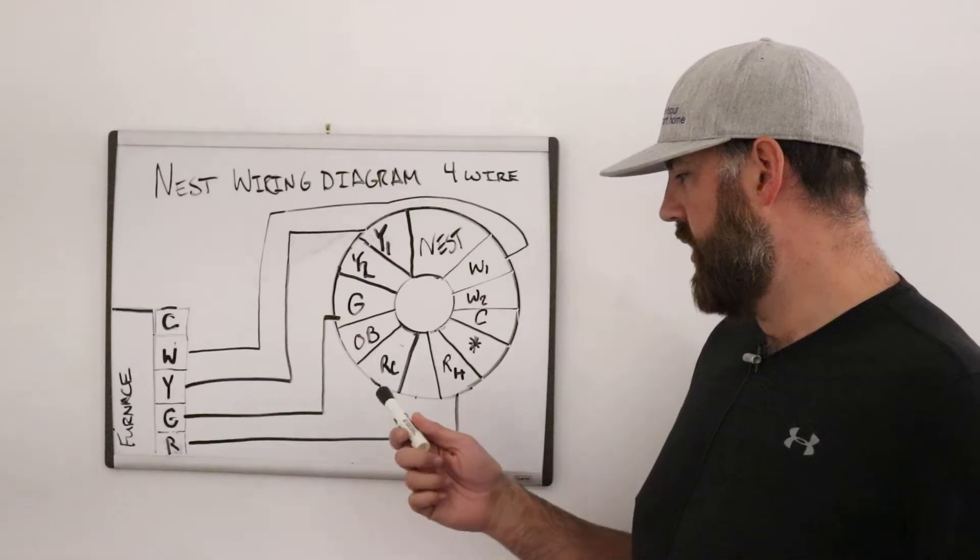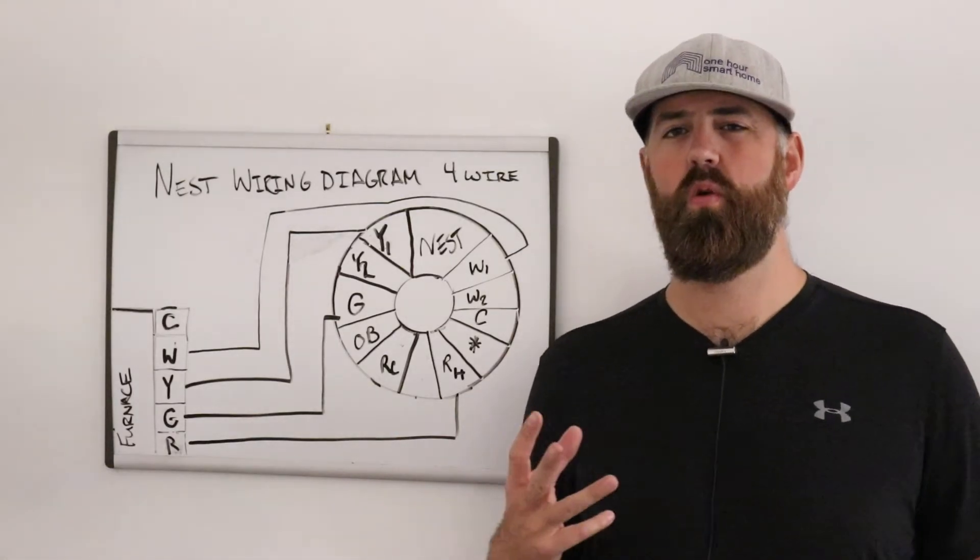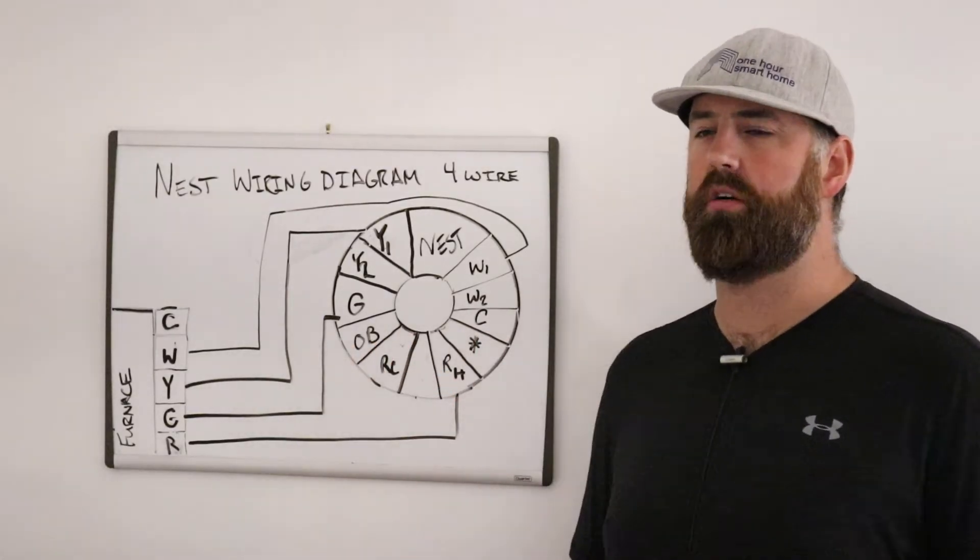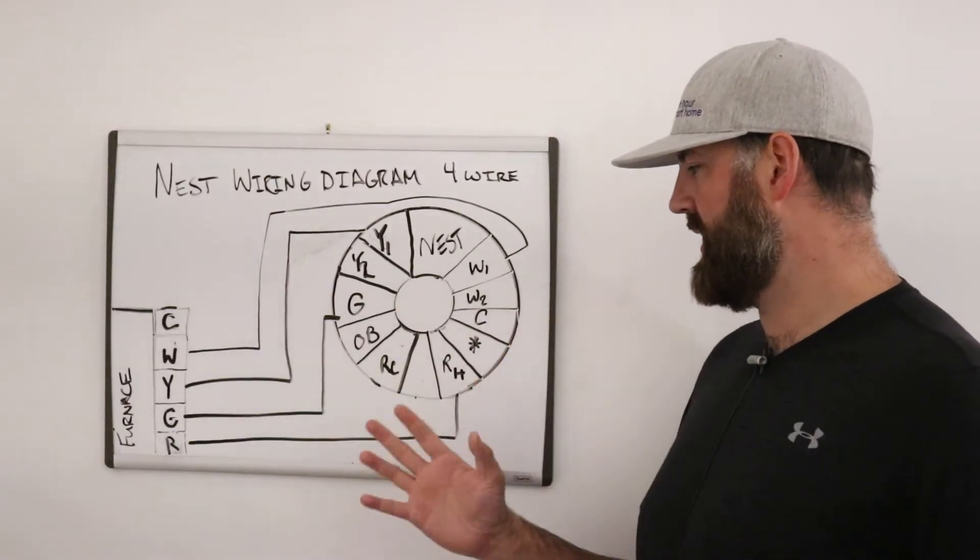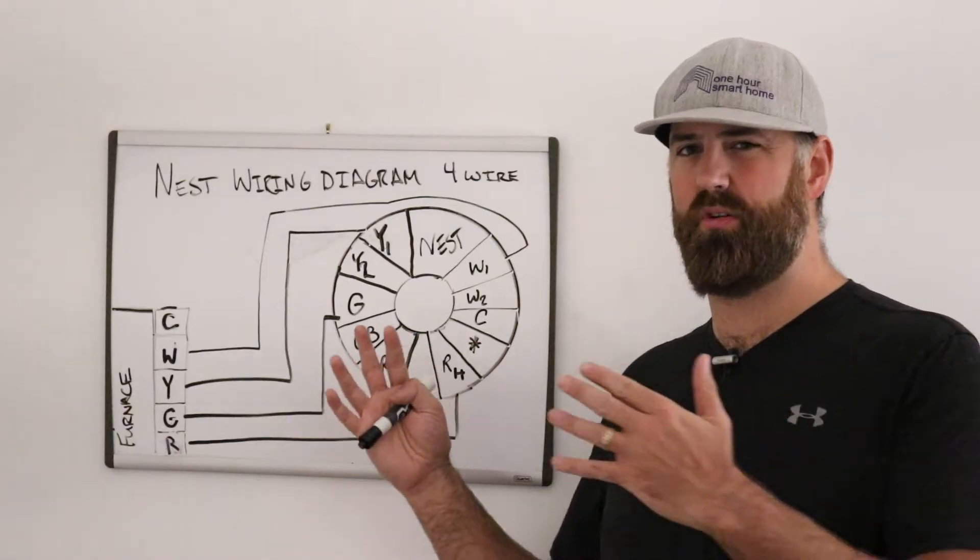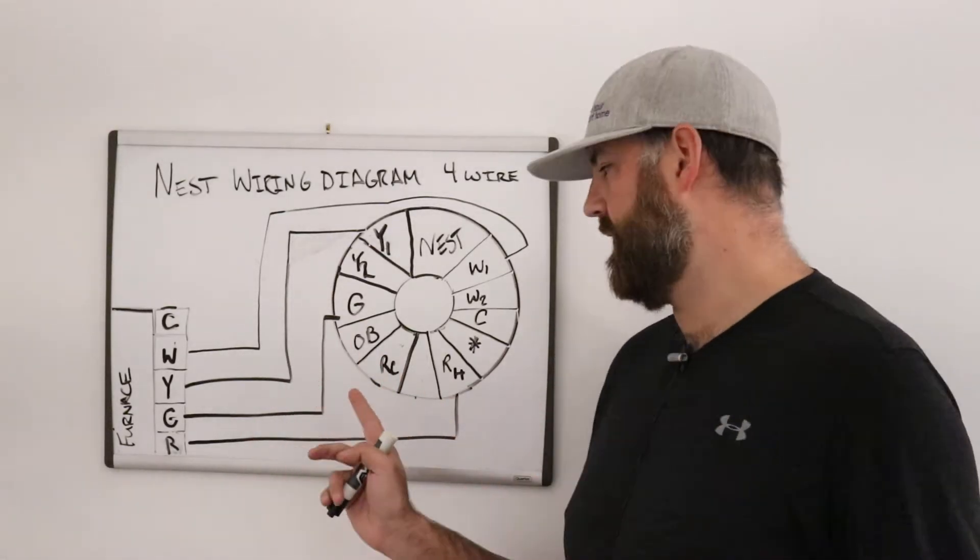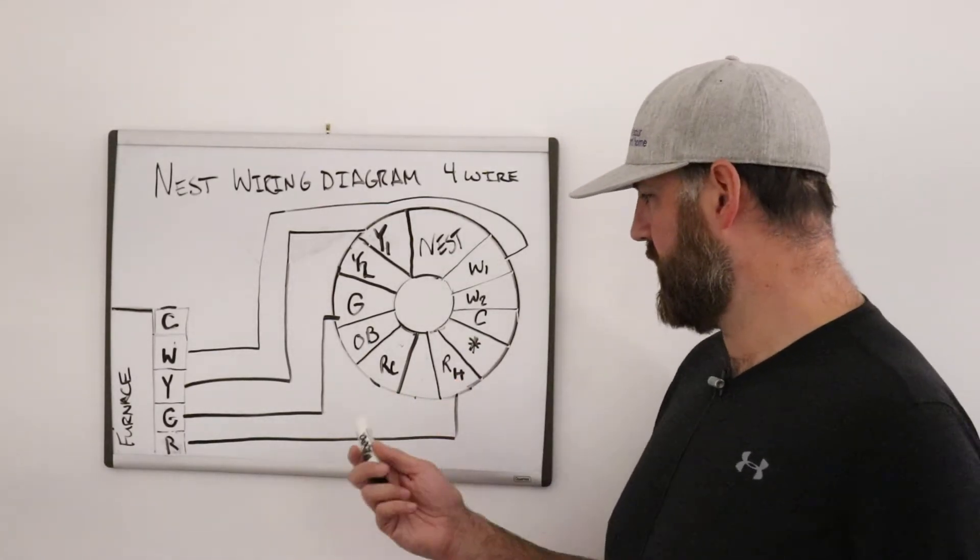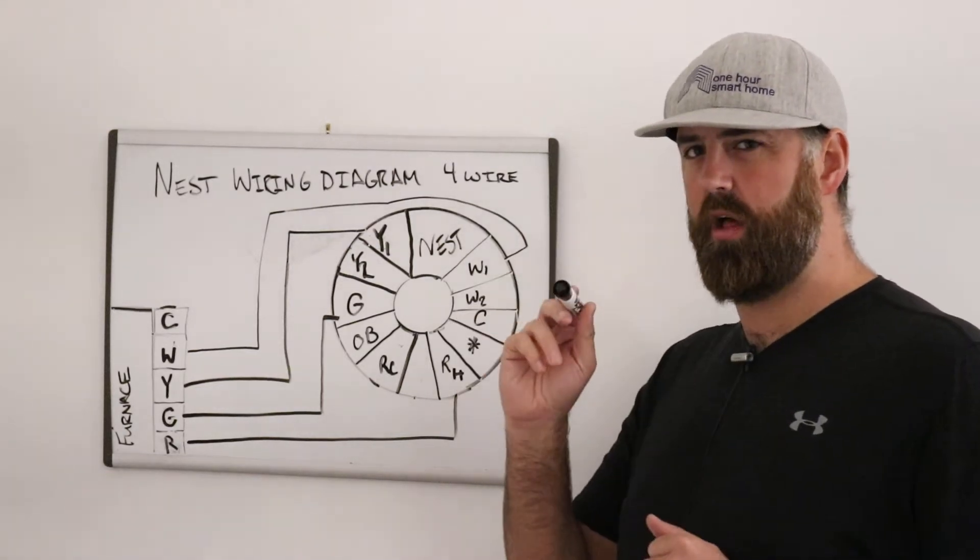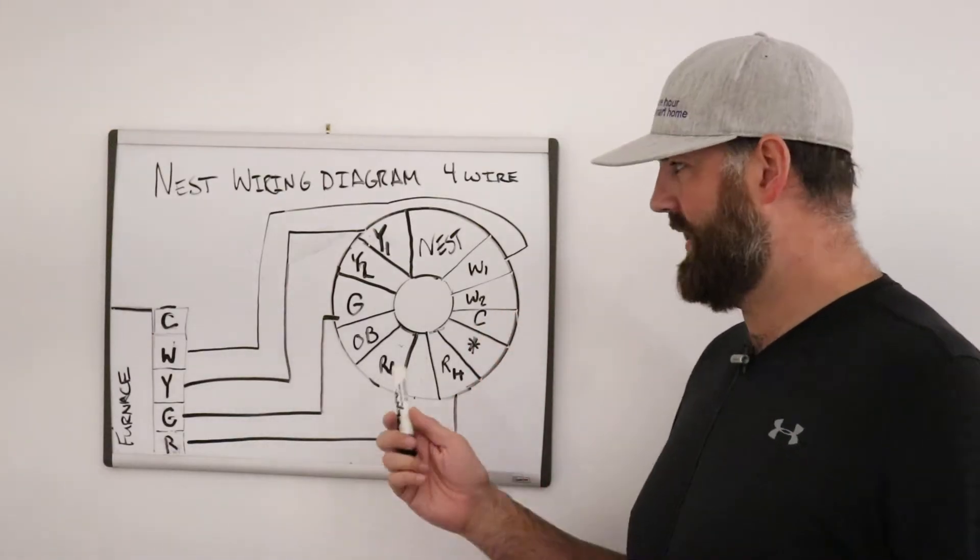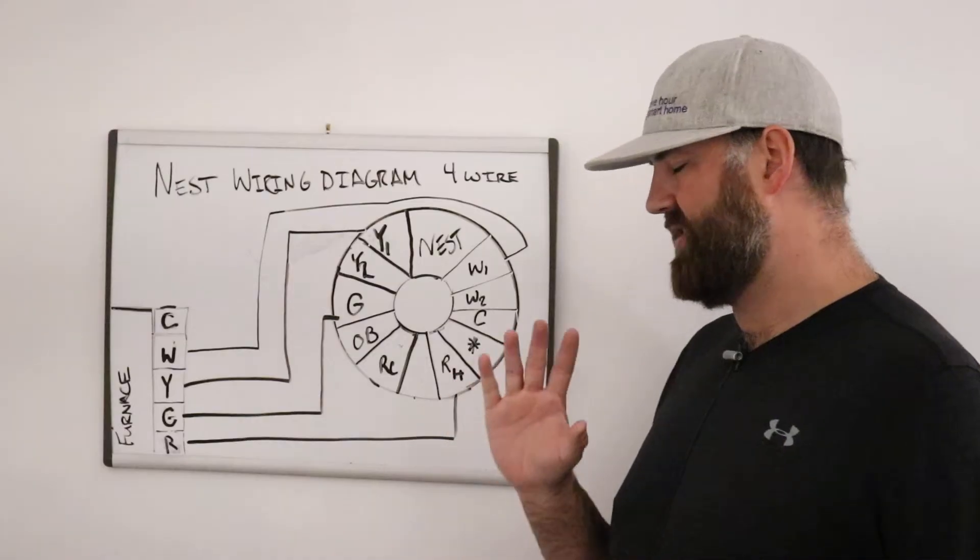After OB, we have what's called the RC wire or the RC terminal. The RC terminal is used for heating or power from a cooling system. So, if you have dual fuel systems, which you wouldn't have with a four wire setup typically, this RC terminal would be used to provide power from the cooling system. Now, RC and RH in a four wire nest system are typically basically the same thing. They're just inputs for power. So, you can have the R terminal power going to either RH or RC and it doesn't matter. It's not going to hurt anything if you put the R wire in RH or RC.